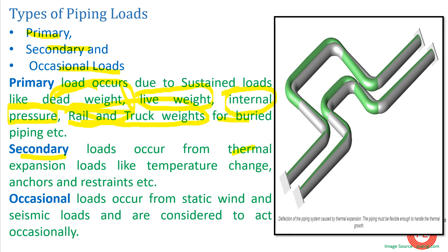Secondary loads occur because of thermal expansion, temperature changes, anchors, and displacement. When conveying steam or chilled water, expansion and contraction of the pipe occur due to temperature changes — either above or below ambient conditions. If the pipe is anchored, meaning it is tightened or supported from both ends with zero axial movement, stresses develop due to these temperature changes. These fall under secondary loads.